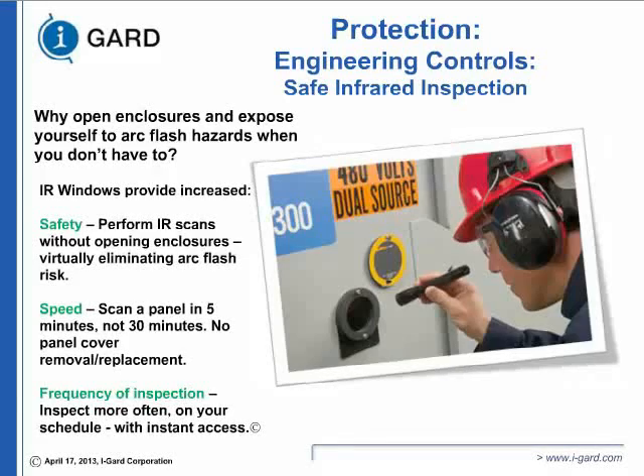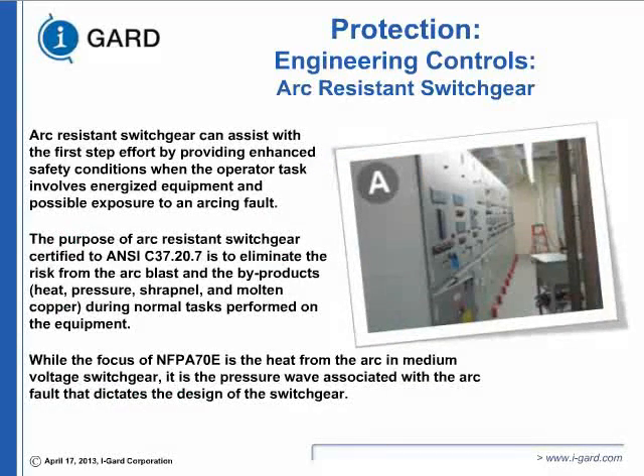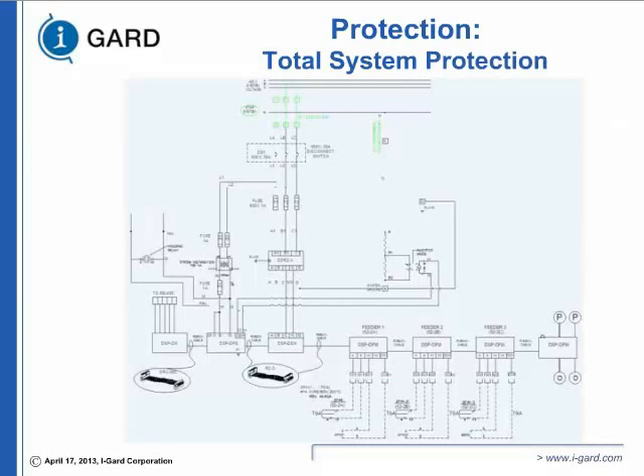You can use arc-resistant switchgear that protects the people from the front. It is only for human protection. It may destroy the equipment. IEEE C37.20.7 is a testing standard. That means somebody at the front will be protected if the equipment is properly designed. Now you can have a total system protection that will cover everything. That means you can have arc-resistant switchgear that will protect the people but doesn't protect the equipment. You can have high-resistance grounding with second fault protection, so you will not have a second fault. You can put a pressure sensor or a light sensor on a circuit.